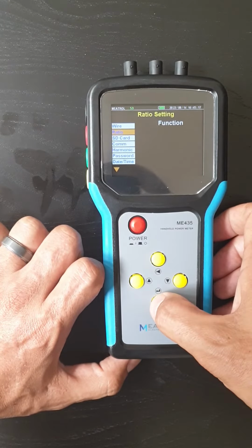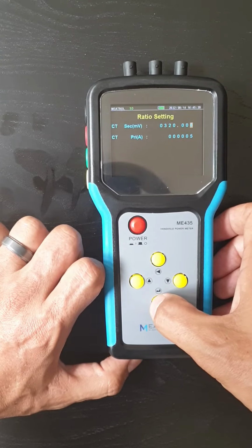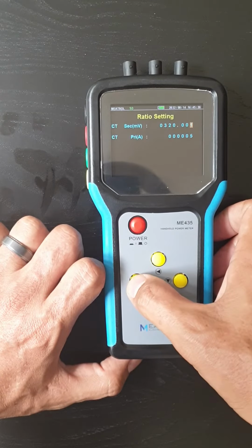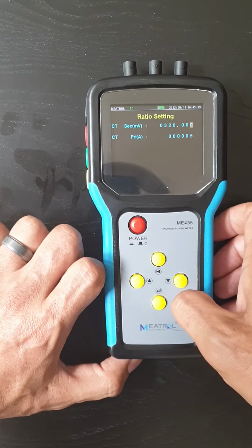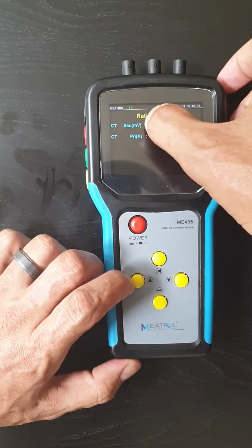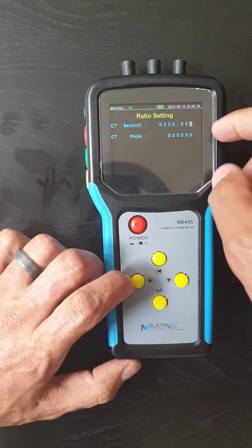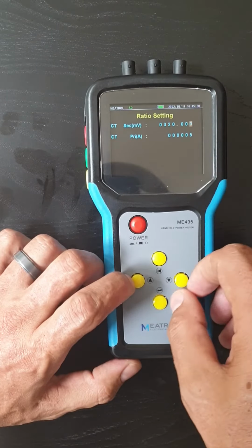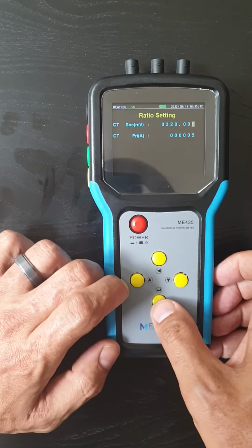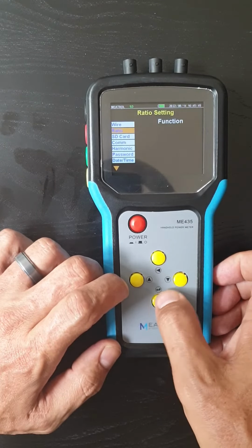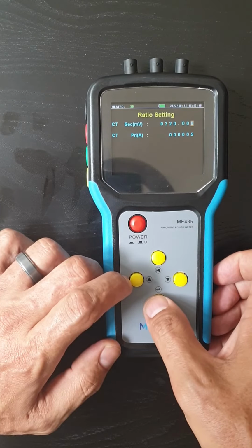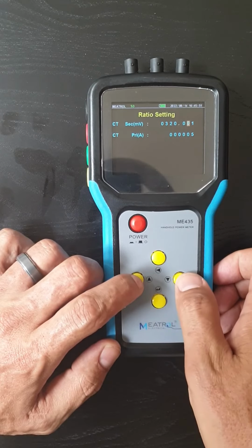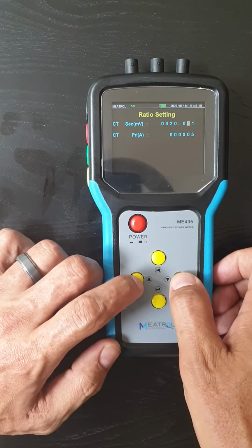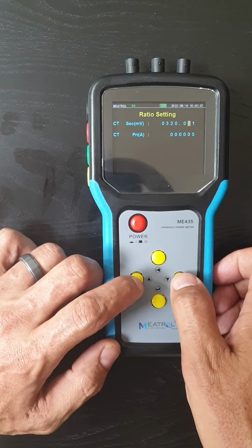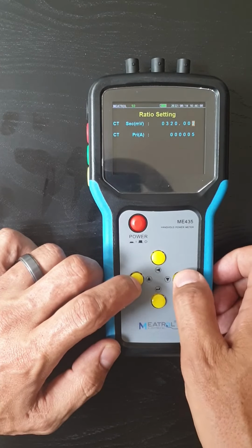Okay, so the next screen is our ratio settings. So you can set the primary CT and the secondary. So this is 320 millivolts to 5. That's dependent on which CT you use. So let's reset that back to where it was.